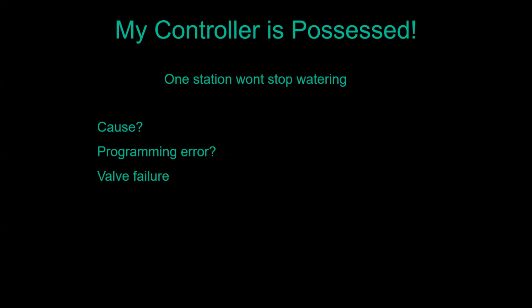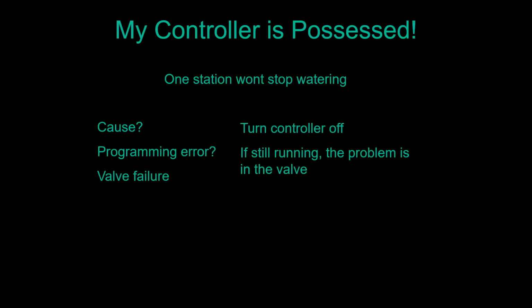It could be a valve failure, what we call a stuck-on valve. So what you want to do is turn the controller to the off position. And if the irrigation is still running, the problem is in the valve and has nothing to do with the controller.